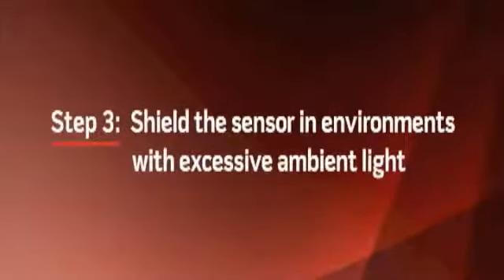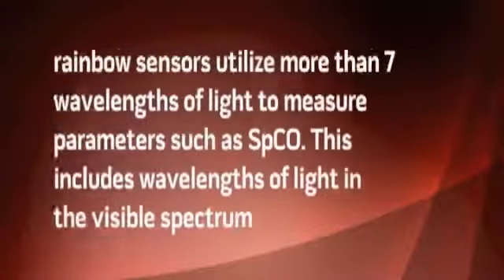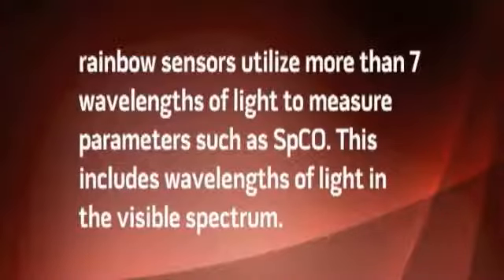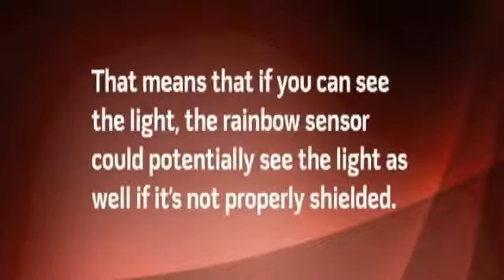Step 3. Shield the sensor in environments with excessive ambient light. Rainbow sensors utilize more than 7 wavelengths of light to measure parameters such as SpCO. This includes wavelengths of light in the visible spectrum. That means that if you can see the light, the rainbow sensor could potentially see the light as well if it's not properly shielded.